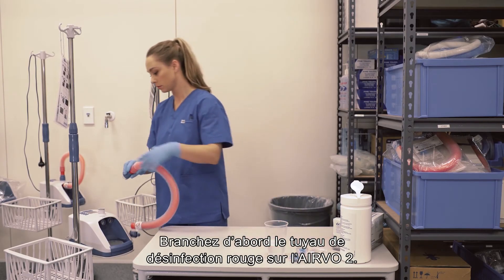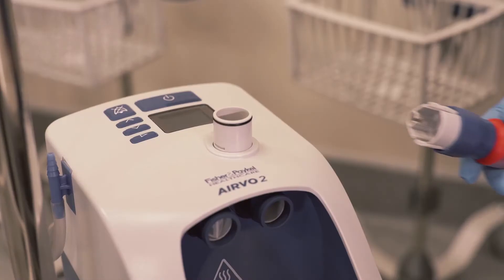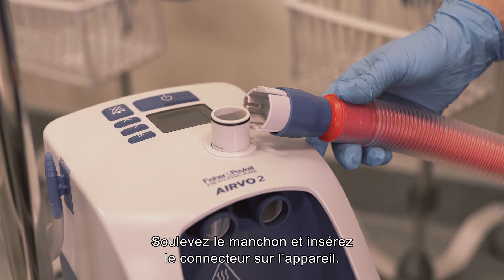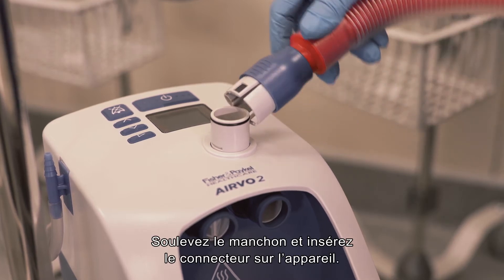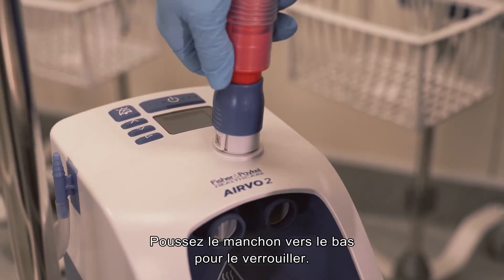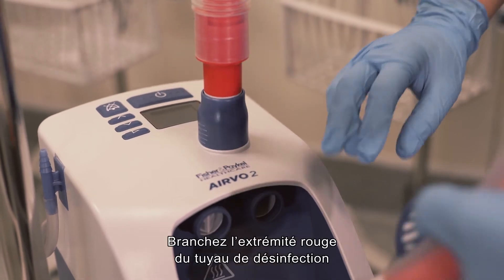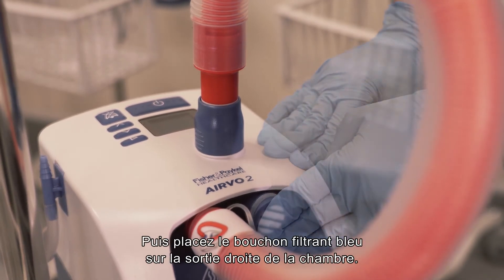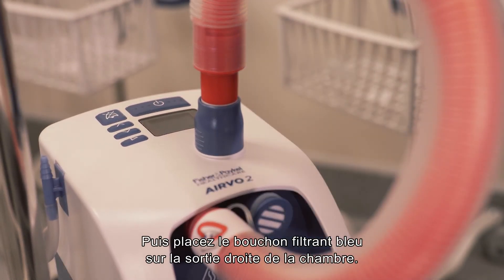First, connect the red disinfection tube to the AIRVO 2. One end of the disinfection tube has a blue plastic connector. Lift the sleeve and slide the connector onto the unit, then push the sleeve down to lock. Connect the red end of the disinfection tube to the left-hand chamber port and push fully into position. Then fix the blue filter cap securely onto the right chamber port.